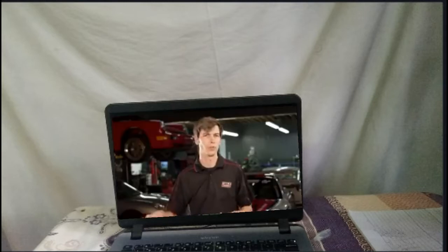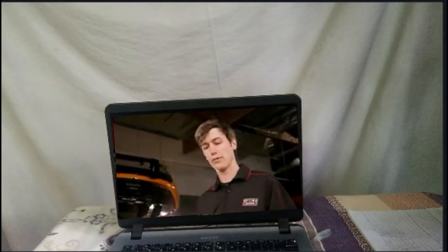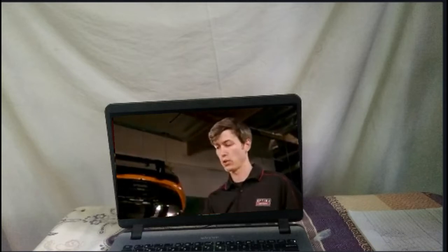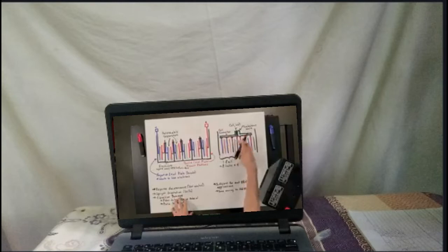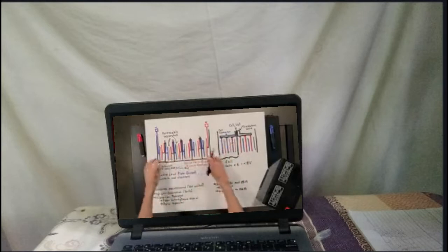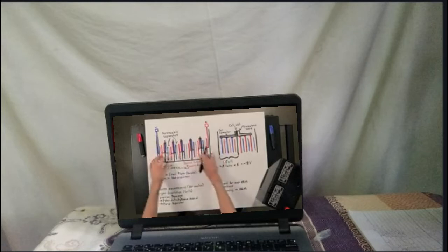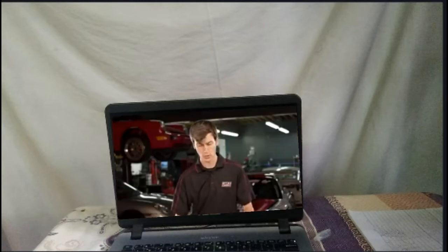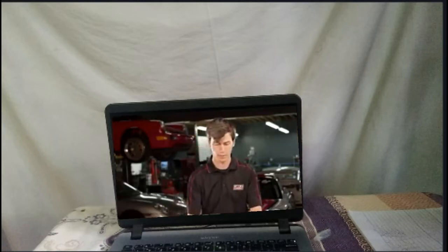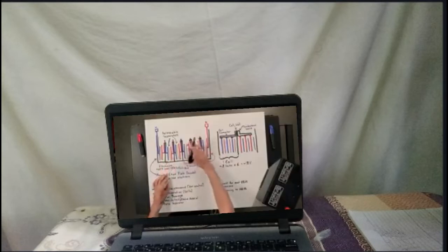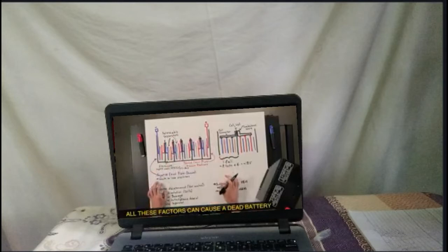And finally, if you're using this type of battery in situations where you're going to have a lot of vibration, it could have some damage from that vibration. You could have the negative plates or the positive plates detach from the cell connector. You can also have some of the active material that's on these plates fall off, and they actually have space at the bottom of these batteries to allow for that debris to kind of collect. And also you could have, in super severe vibration scenarios, that separator pierced and then short out the circuit by connecting the positive and the negative plates.